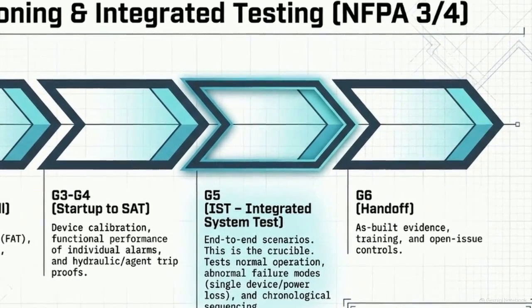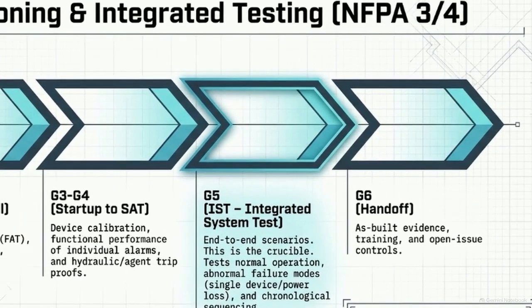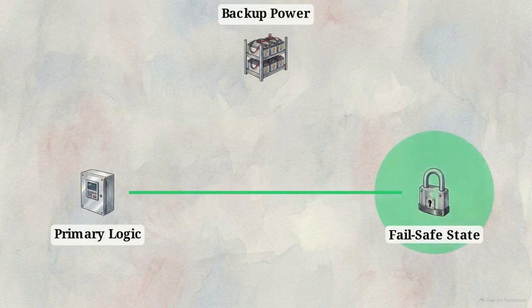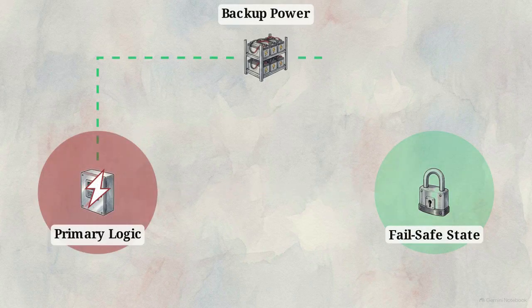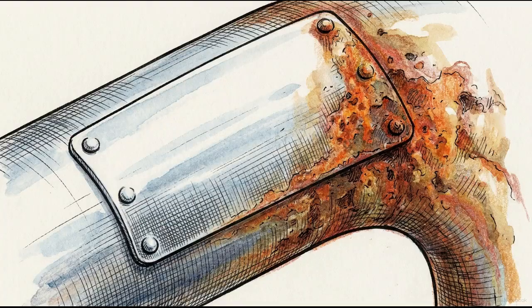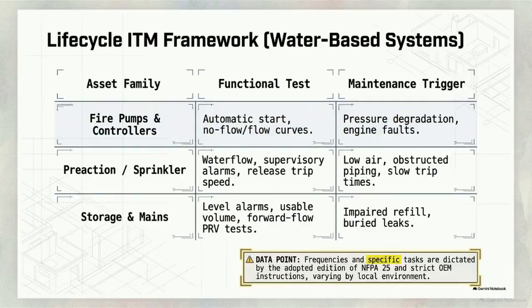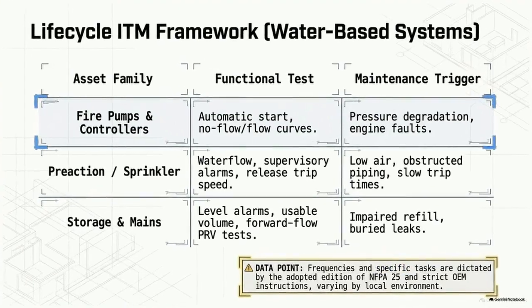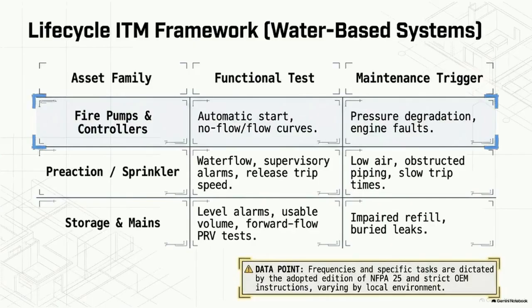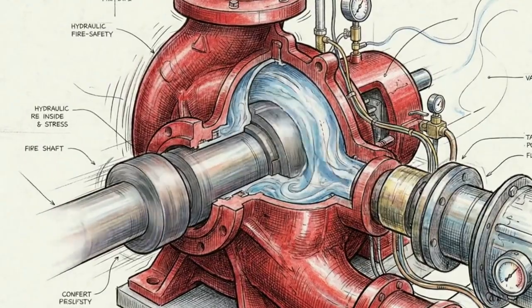The Integrated System Test is the ultimate crucible. It forces end-to-end scenarios to verify that the chronological sequencing executes properly. The test must intentionally force abnormal failure modes, like a device dropping offline or total power loss, to prove that the fail-safe states hold. A system's reliability begins degrading the exact moment commissioning ends. To combat this, NFPA 25 mandates strict ongoing functional testing for water-based systems, including specific triggers for fire pumps and their controllers. Testing these assets is a violent mechanical reality.